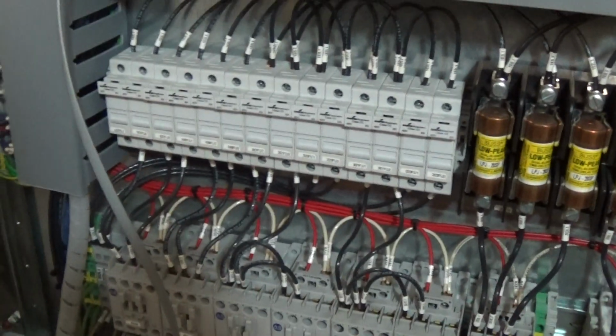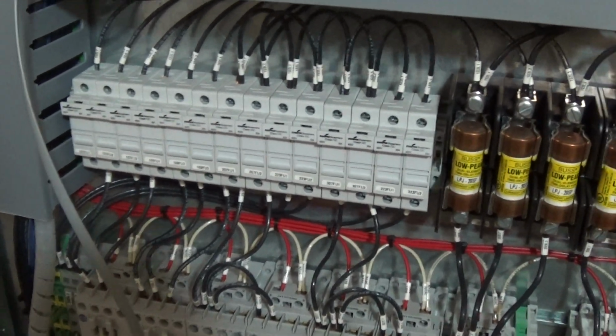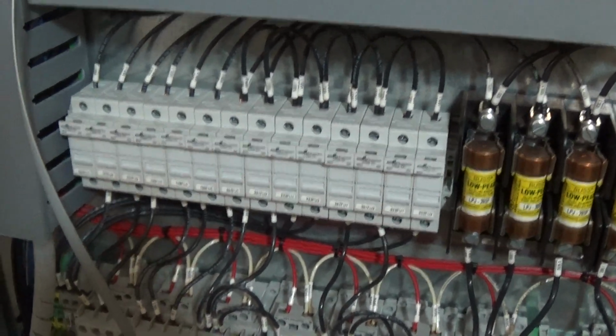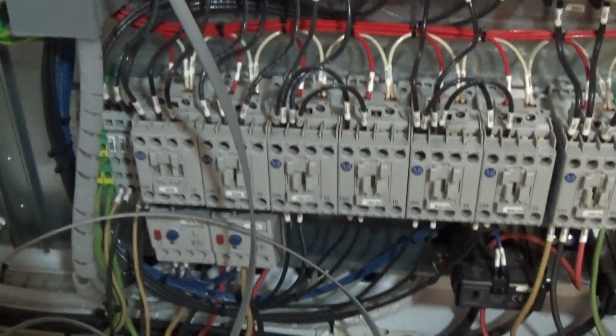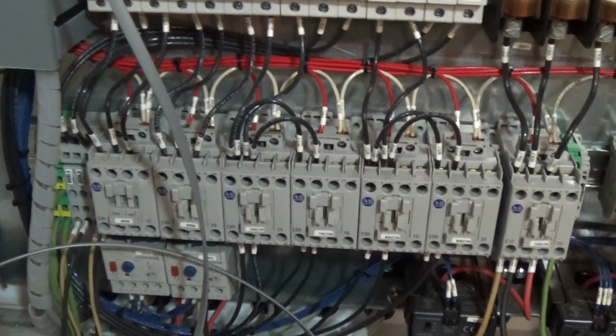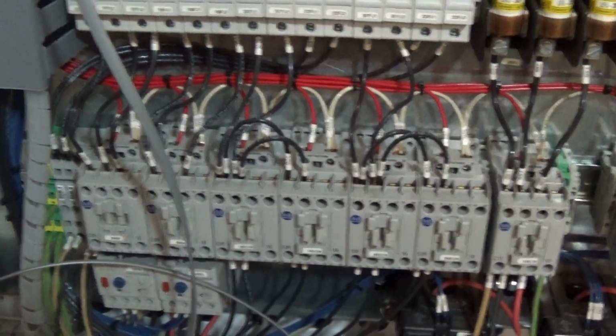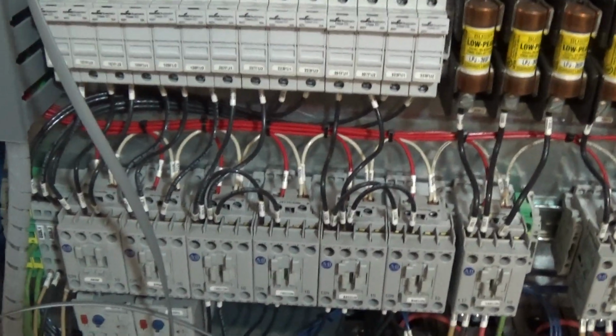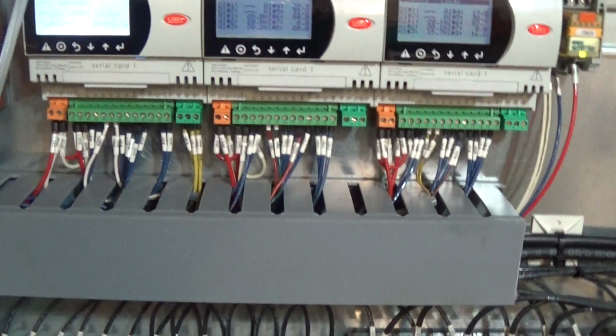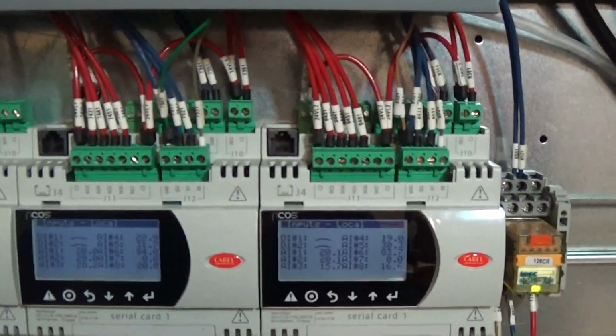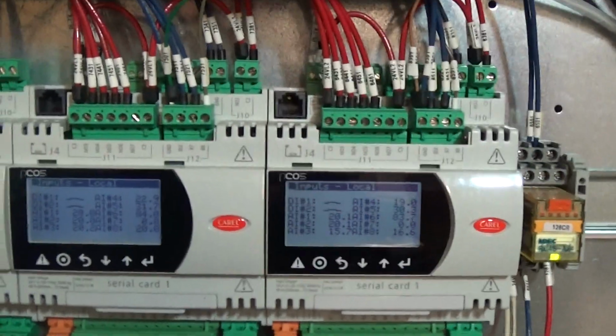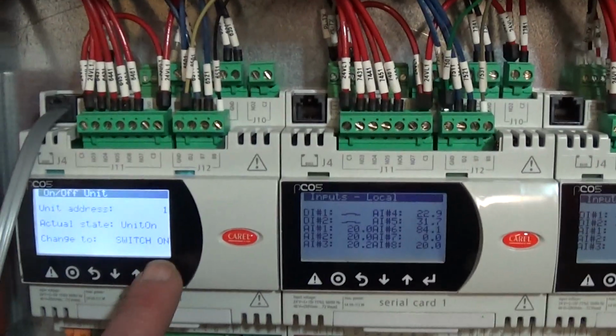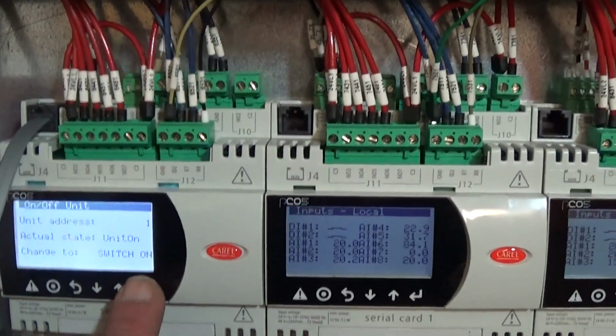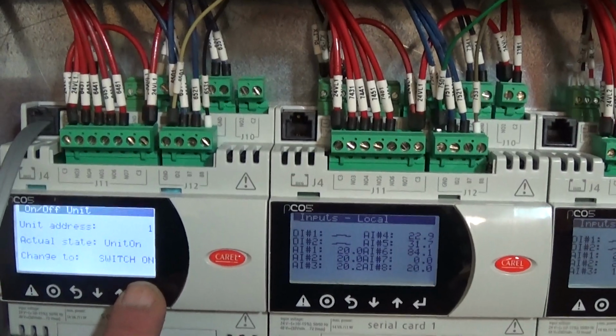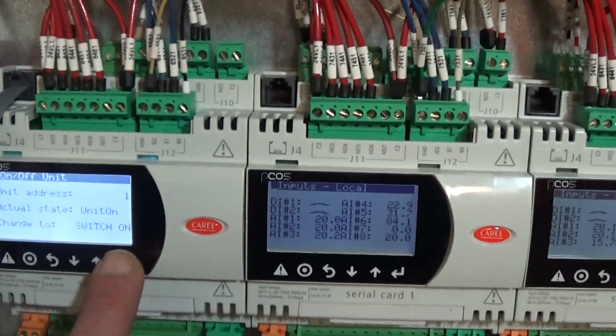One pump is usually all you're going to run, and it should alternate between the two pumps. And it tries to keep the hours kind of even on that. Two pump contactors are the first two, and they include a pair of overloads to prevent the pumps from overheating electrically. What we're going to do, you can see the different inputs on the two monitors there. Now that the unit is on, we actually want to go in and lower the set point, because I've got it set high at 80 right now, just so that I can get some run time and have enough load that I'll run more than one compressor, being that I just have a loop.